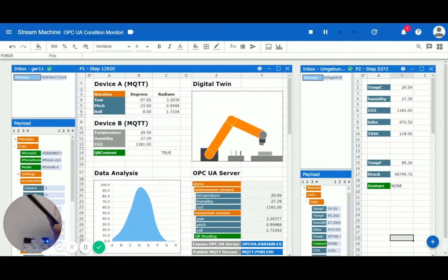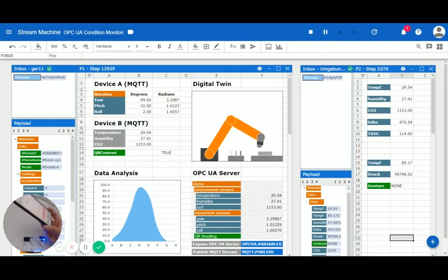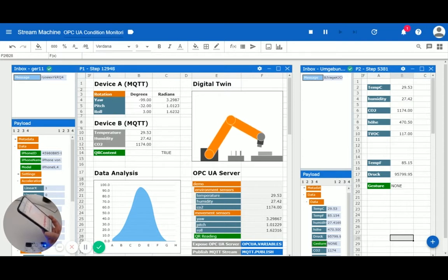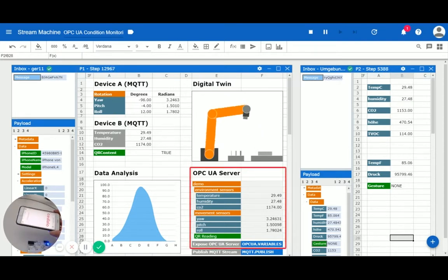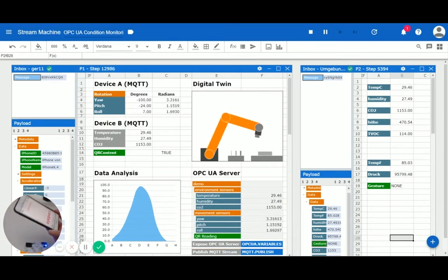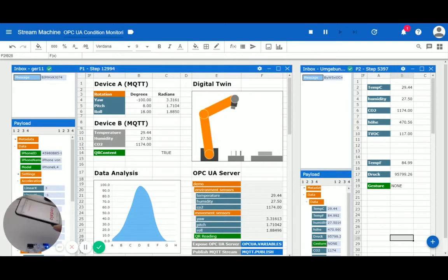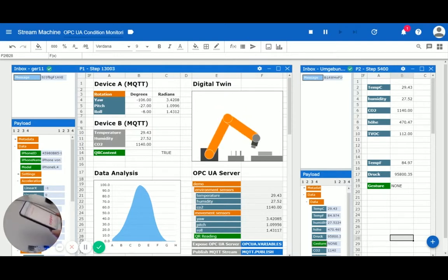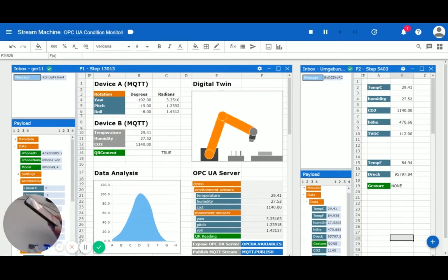Noteworthy is also that the asynchronous data streams are merged and made available as one OPC UA server. As a result, we do not only synchronize two data streams, but also convert from one protocol into another.